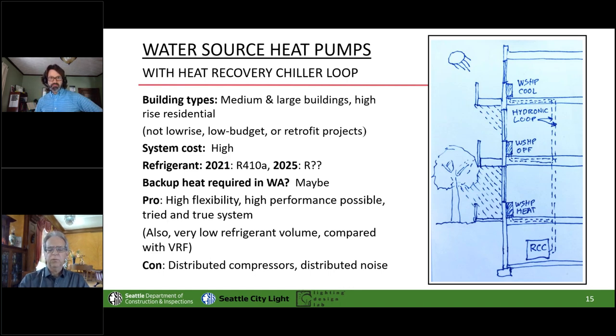Yep. One more thing on this one, Ben. You had a little warning about noise with having those little heat pumps in each space. Thank you. Yeah, so the compressor lives in the water source heat pump. And just like the packaged terminal heat pumps and vertical terminal heat pumps we spoke about in the multifamily version, that means you don't just get fan noise, you also get compressor noise every time the thing turns on and off. And they're isolated and insulated, the actual compressor, so it's not horrible, but it's more noise than some other equipment you could choose.